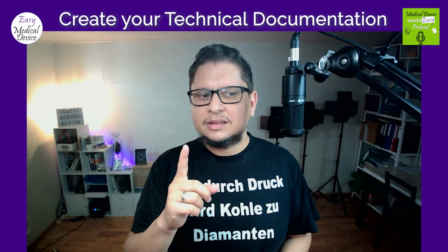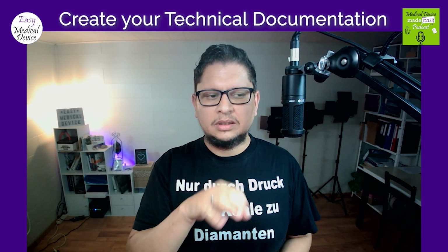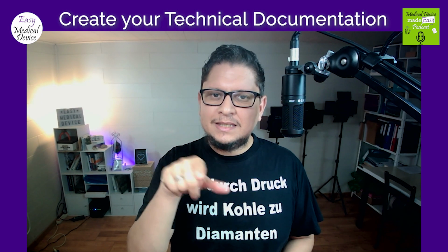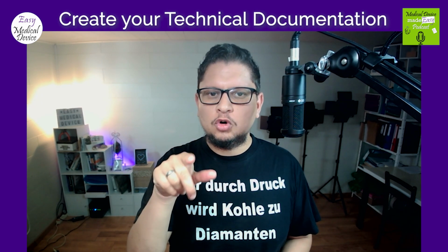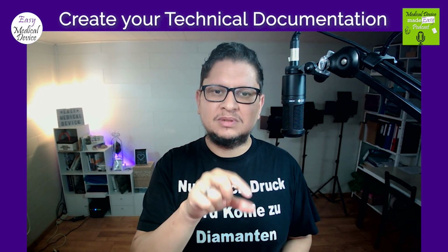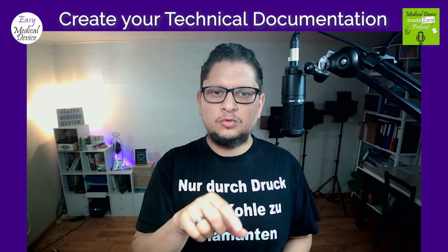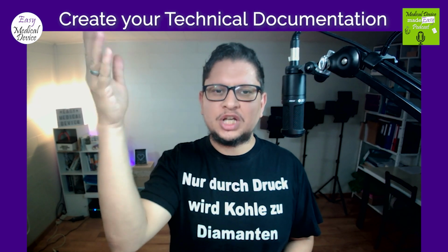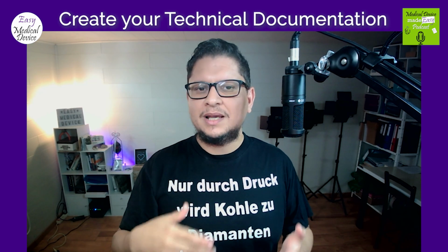Only one thing, I didn't find it there, but it is required for your instructions for use. It is the CE logo. The CE logo also needs to be visible on the instructions for use for your product. It's not mentioned in Annex 1, but it is mentioned in one of the chapters of the legislation, I can't remember which one, which says your CE marking should also appear on your instructions for use.